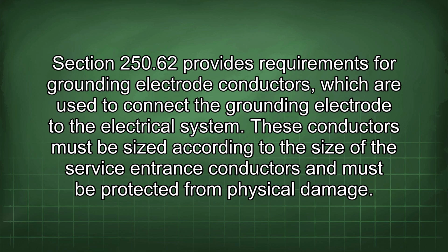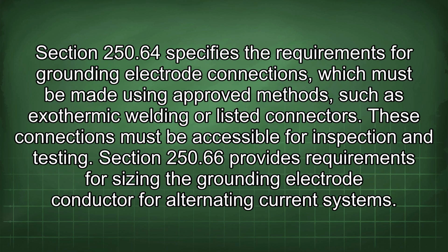These conductors must be sized according to the size of the service entrance conductors and must be protected from physical damage. Section 250.64 specifies the requirements for grounding electrode connections, which must be made using approved methods such as exothermic welding or listed connectors. These connections must be accessible for inspection and testing.